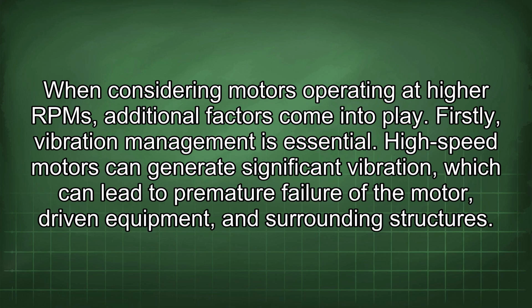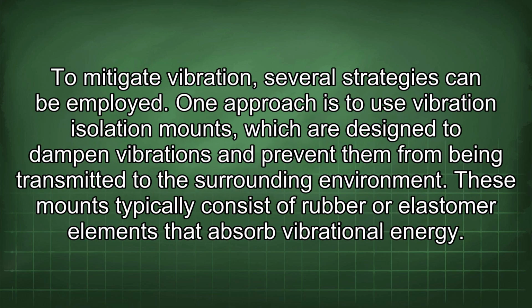When considering motors operating at higher RPM, additional factors come into play. Firstly, vibration management is essential. High-speed motors can generate significant vibration, which can lead to premature failure of the motor, driven equipment, and surrounding structures. To mitigate vibration, several strategies can be employed. One approach is to use vibration isolation mounts, which are designed to dampen vibrations and prevent them from being transmitted to the surrounding environment. These mounts typically consist of rubber or elastomer elements that absorb vibrational energy.